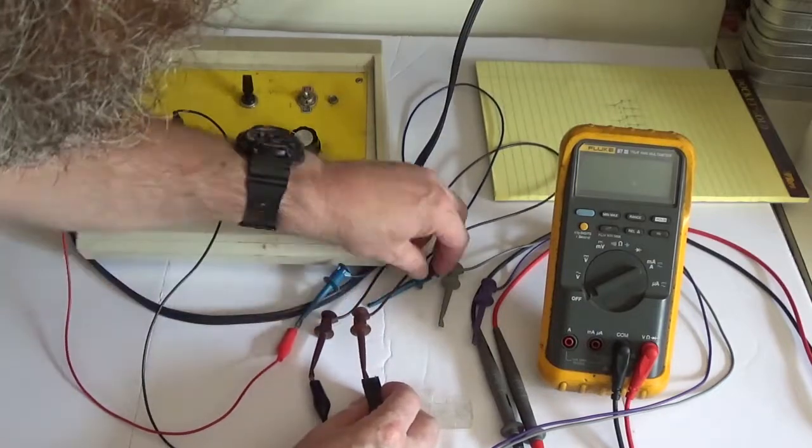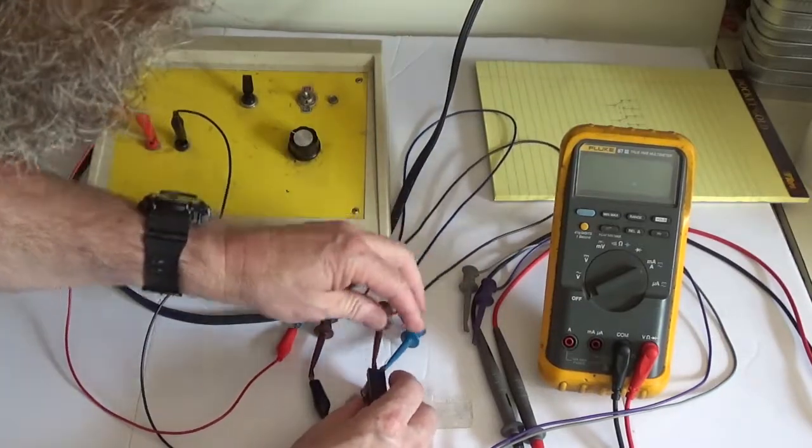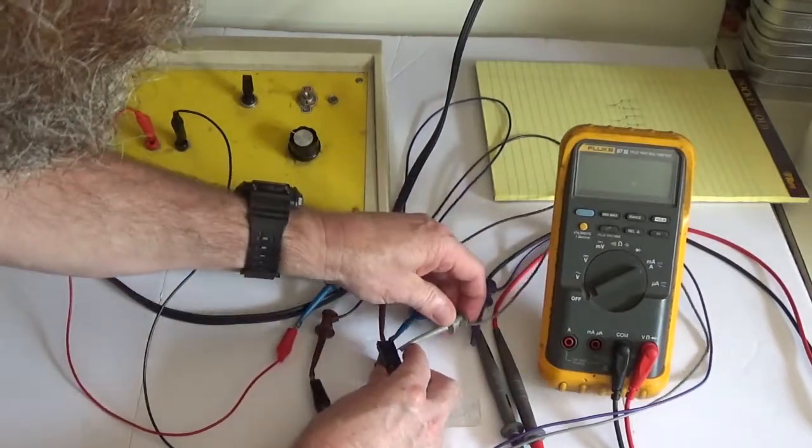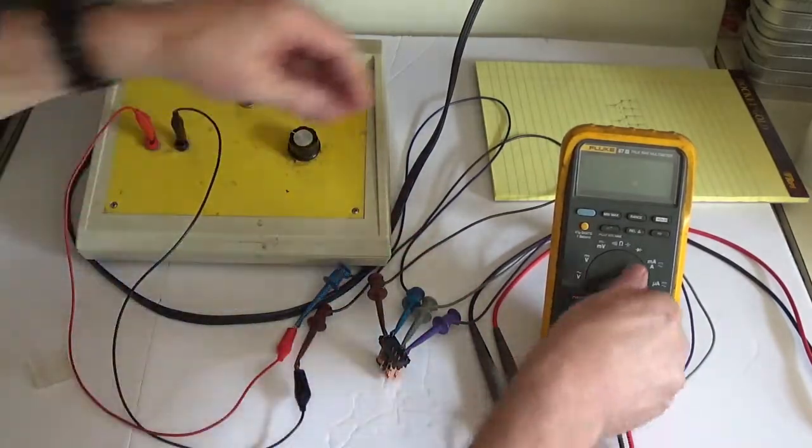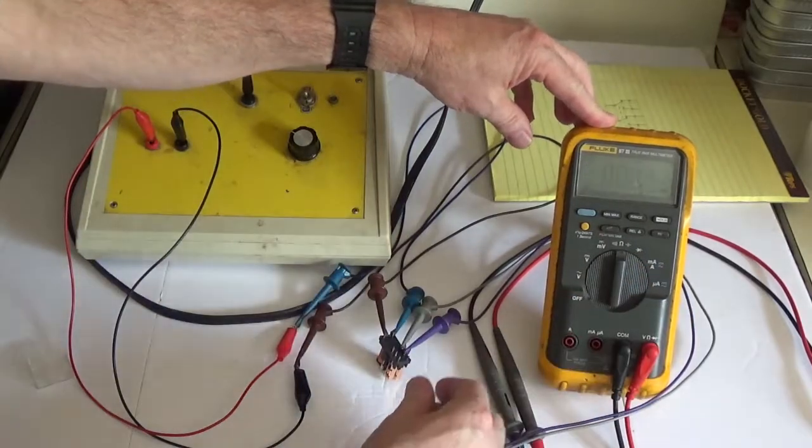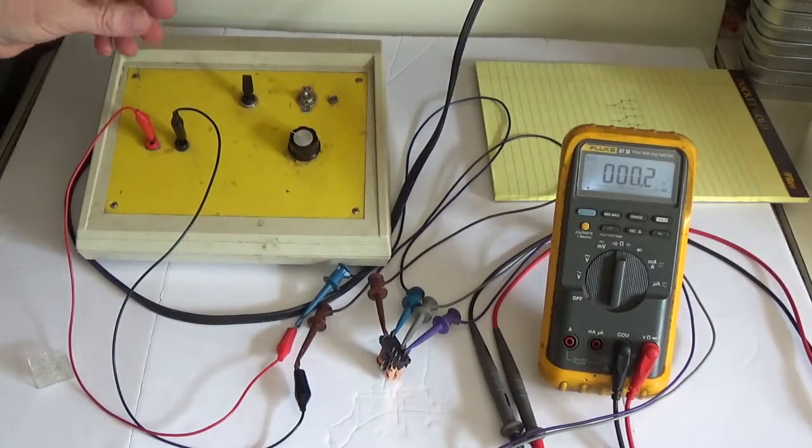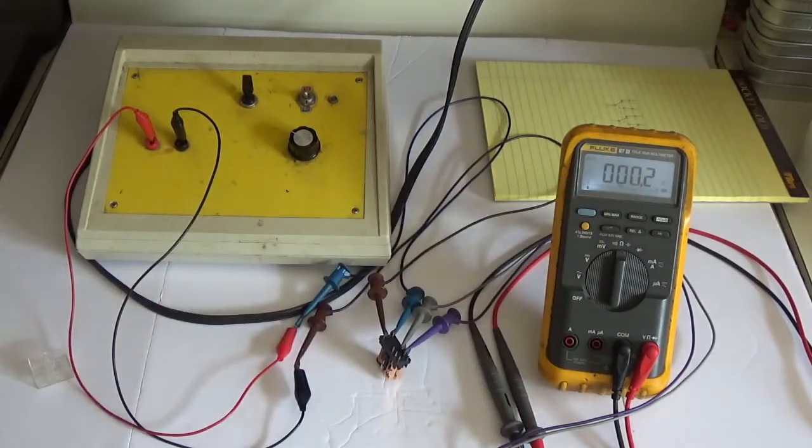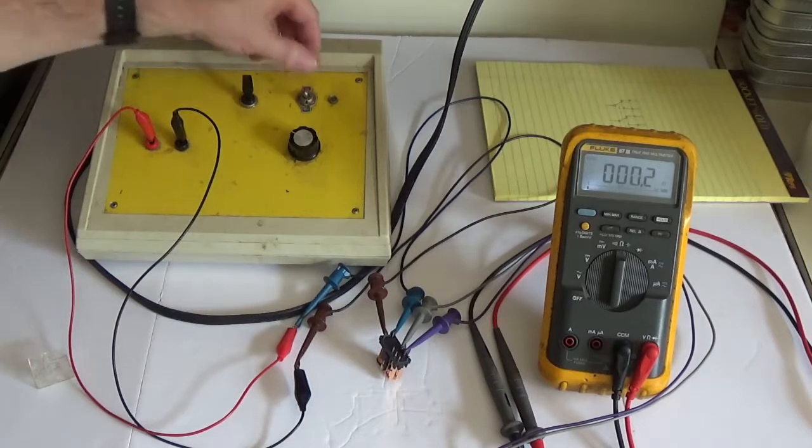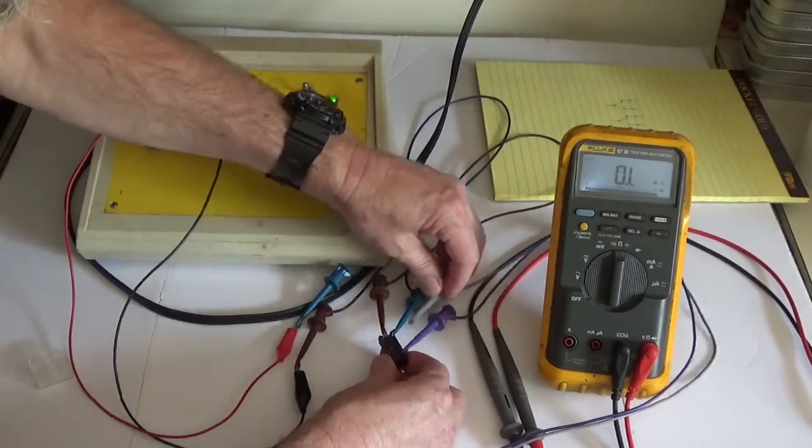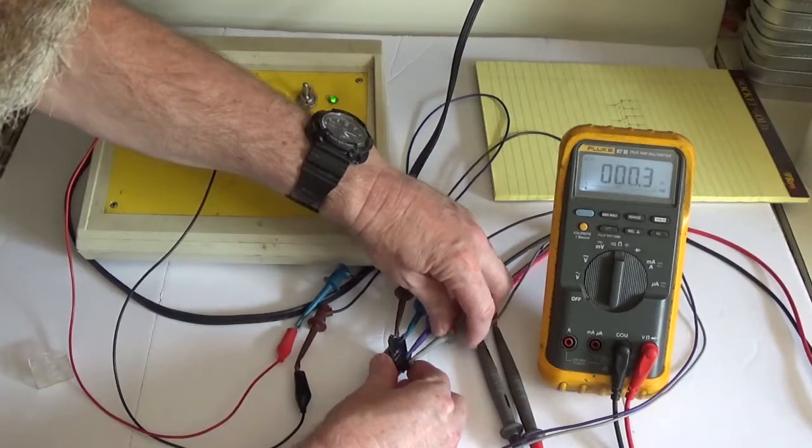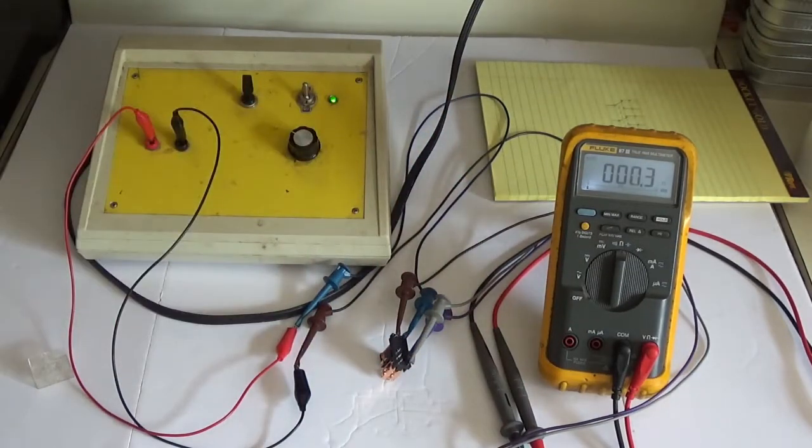Okay let's try that. Hook up our coil again, hook up our meter leads to the normally closed contact. Put our meter back in ohms mode. There we got 0.2 ohms, that's my meter lead resistance. Put the 24 volts to the coil, just opened up, move it over to the other side. Look at that, is it that much better? That's the side that was bouncing around from up there to 100 down to 80 and whatnot. Okay so that side is cleaned up.